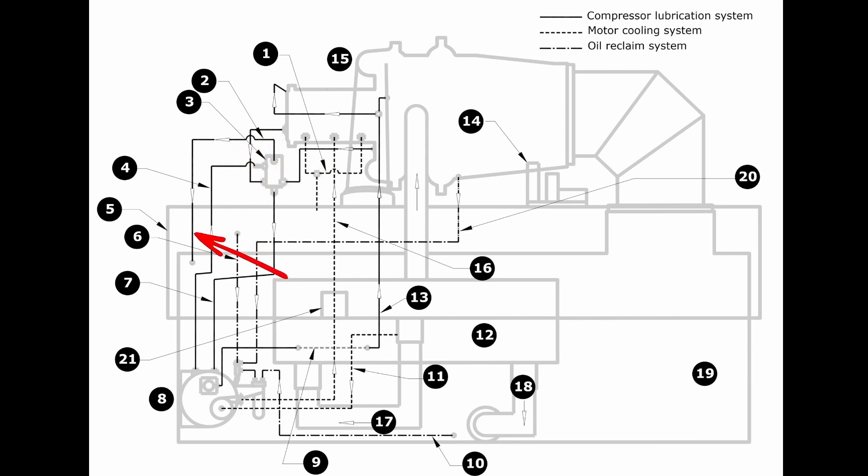In addition, it is our vent line passing from our oil tank coming up through and allowing our vapor to get caught into the oil tank, including the vapor that gets injected from the eductor system to come from the oil tank and flow back up through into the evaporator in order to prevent vapor refrigerant from stacking into the oil tank assembly.